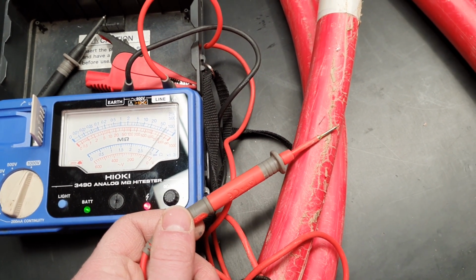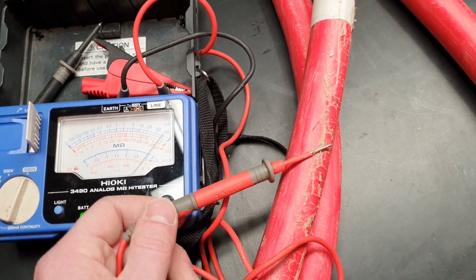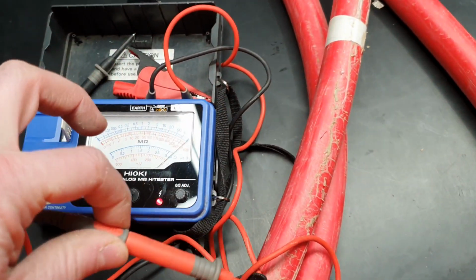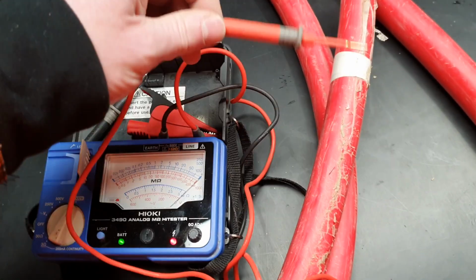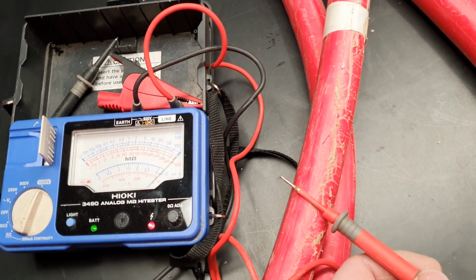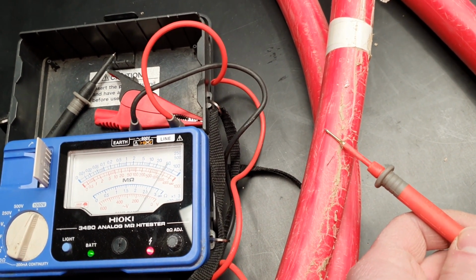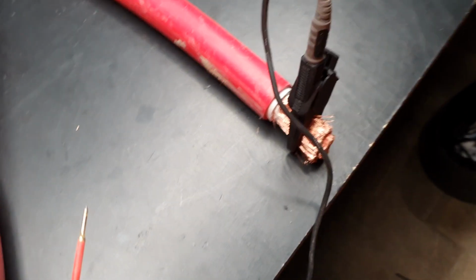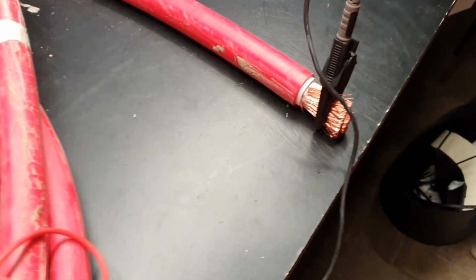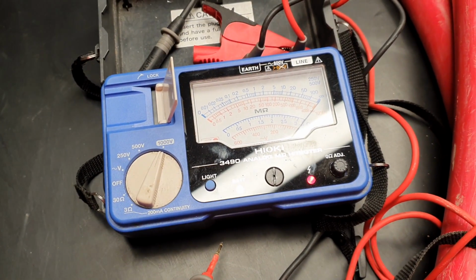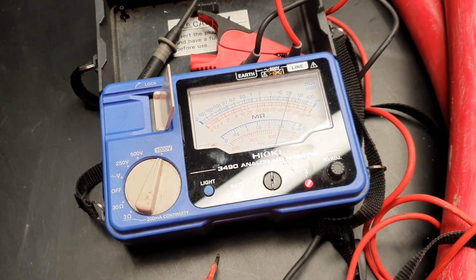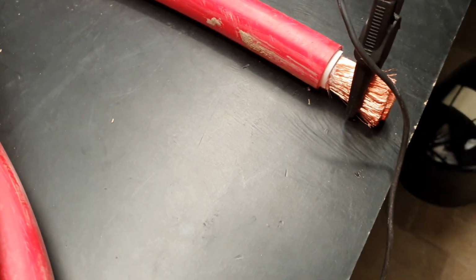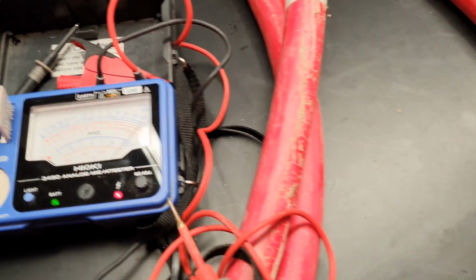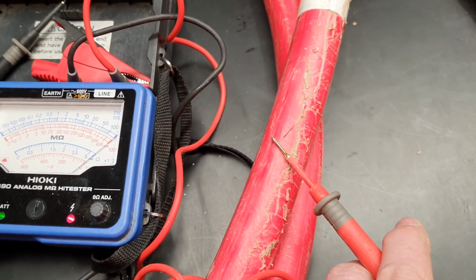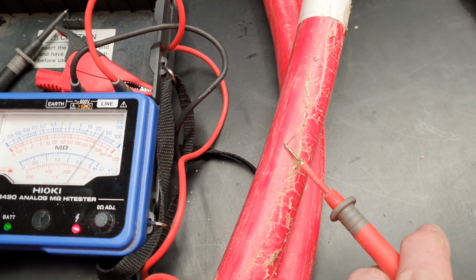So a pinprick on 1,000 volts - I've been wandering over the cable trying to cover as much as I can, looking for this pinprick. Now initially I had the thing on the table, and I touch the table and I'm getting a reading through the actual plywood, which is incredible. That's how sensitive this thing is. So I was hoping I'd wander around the cable and find something like this where it would pick up.